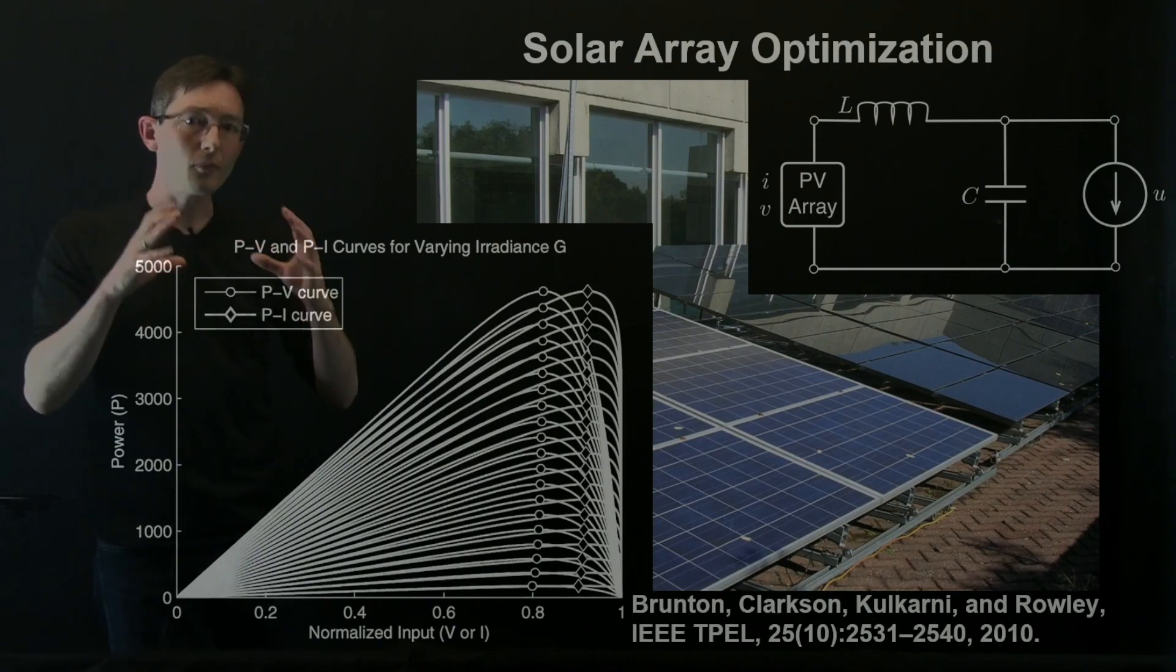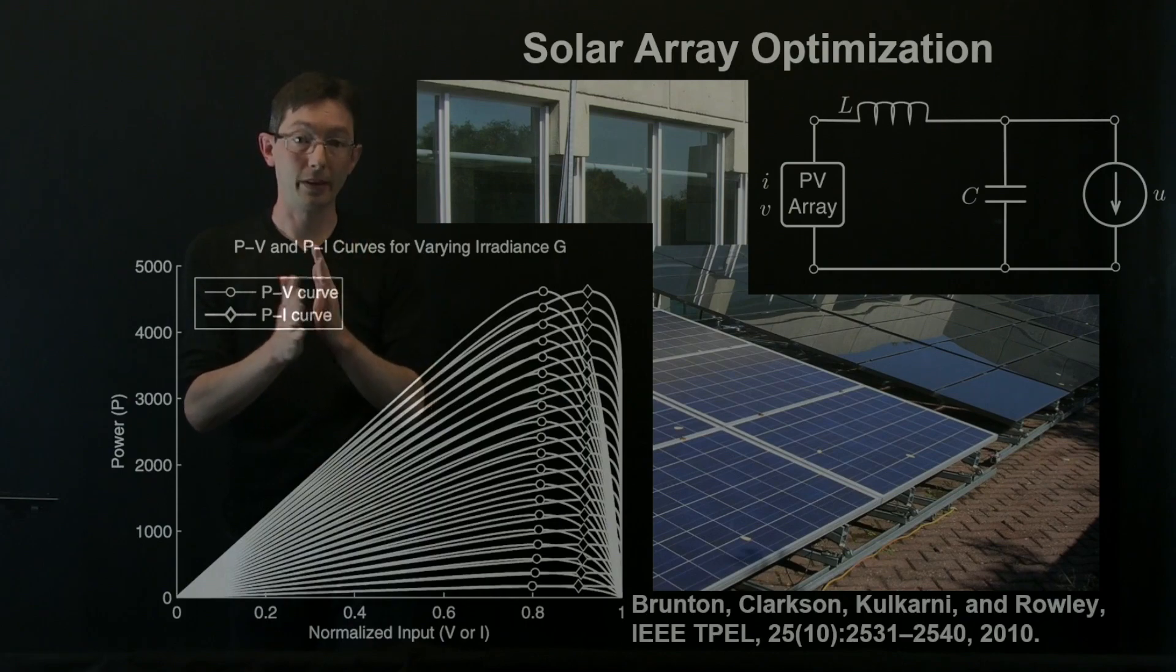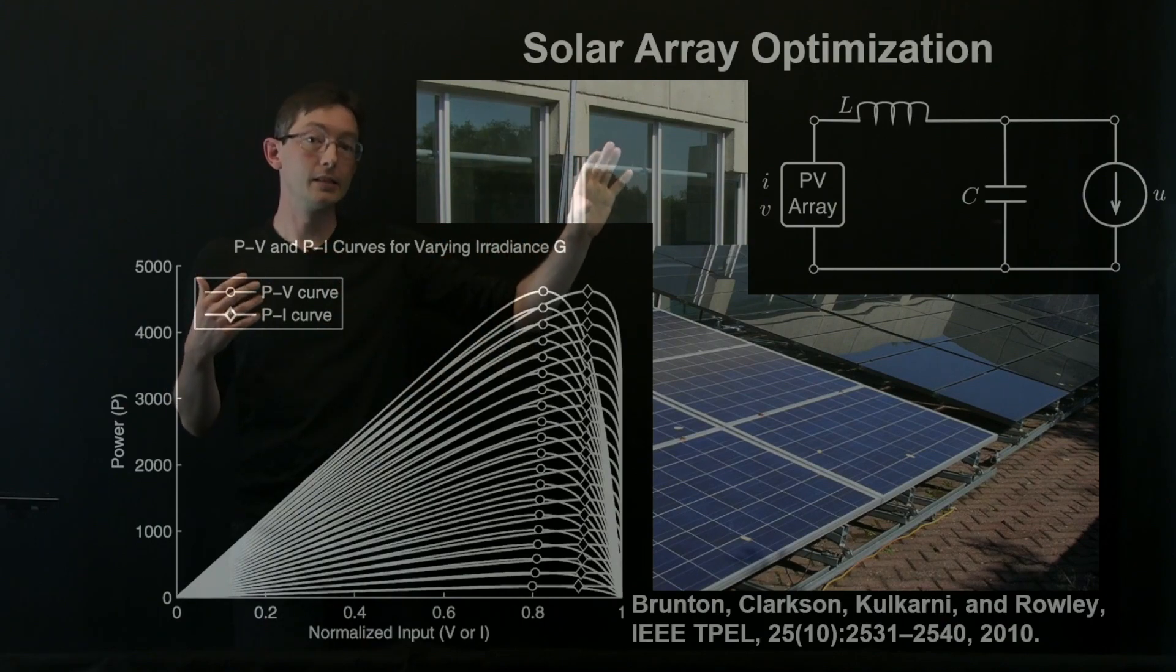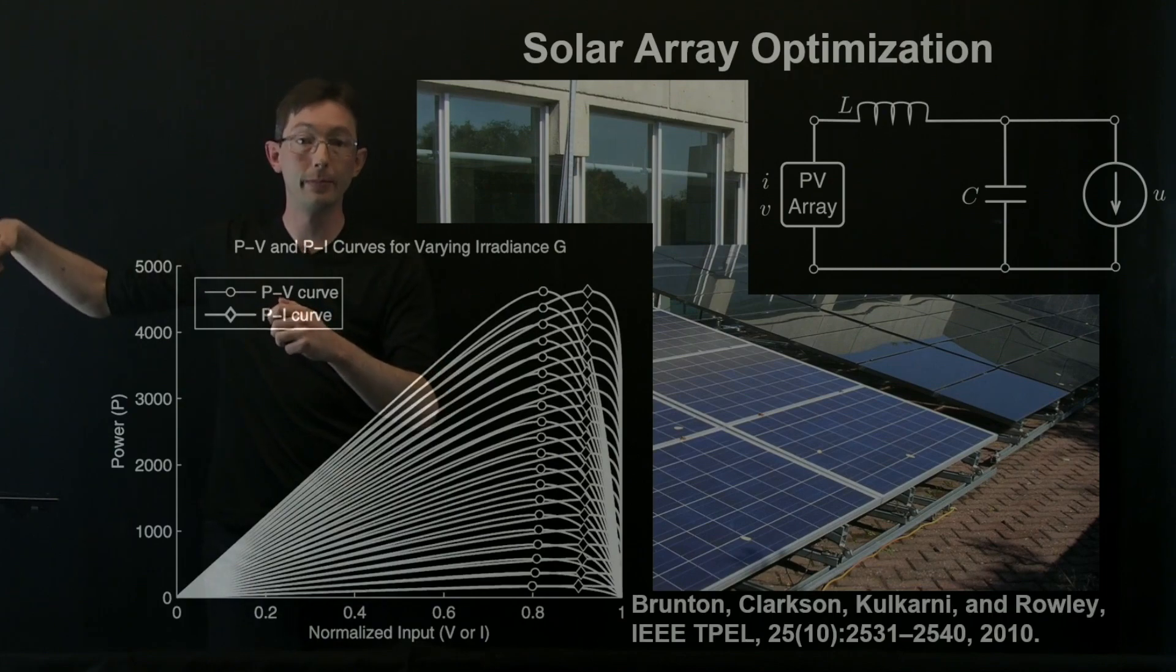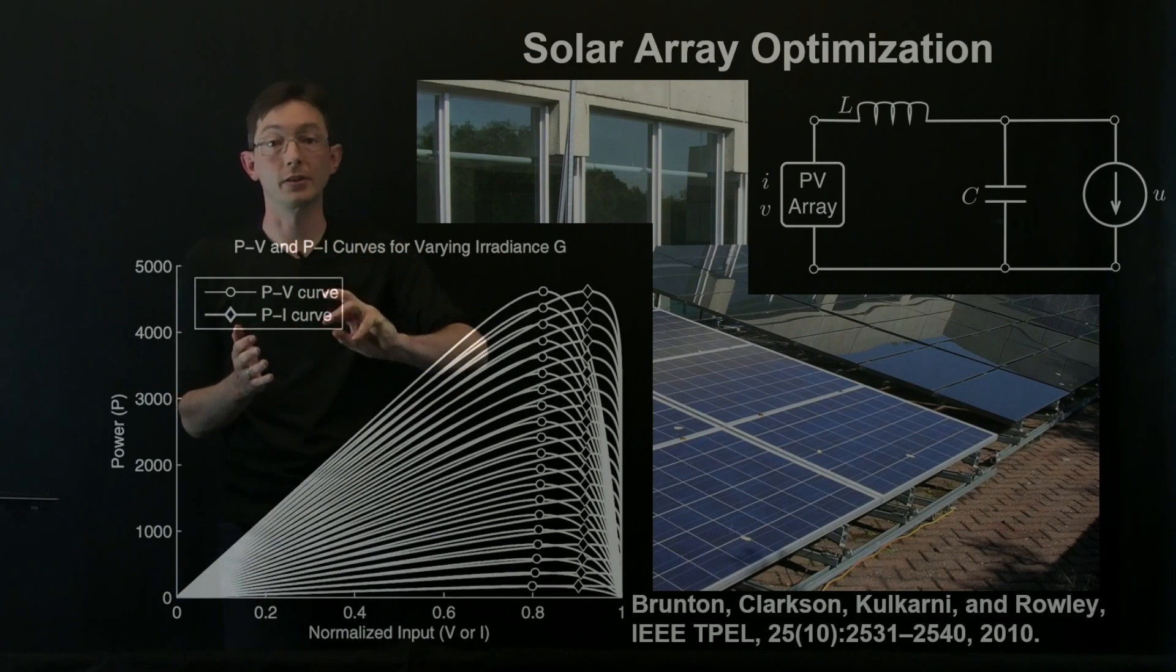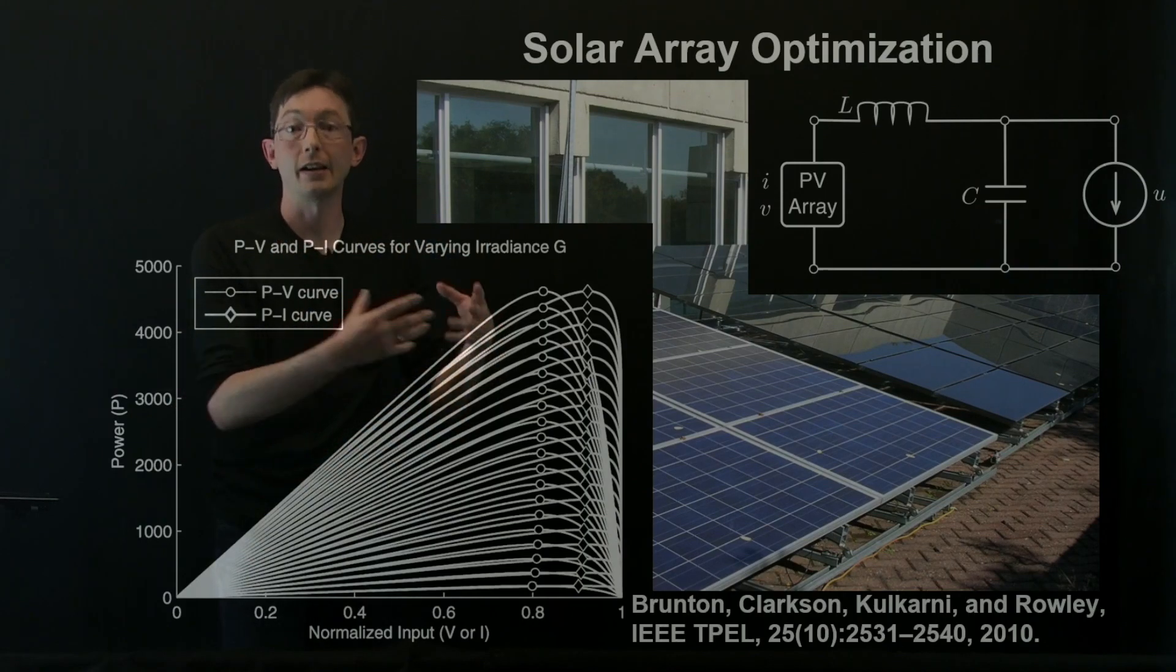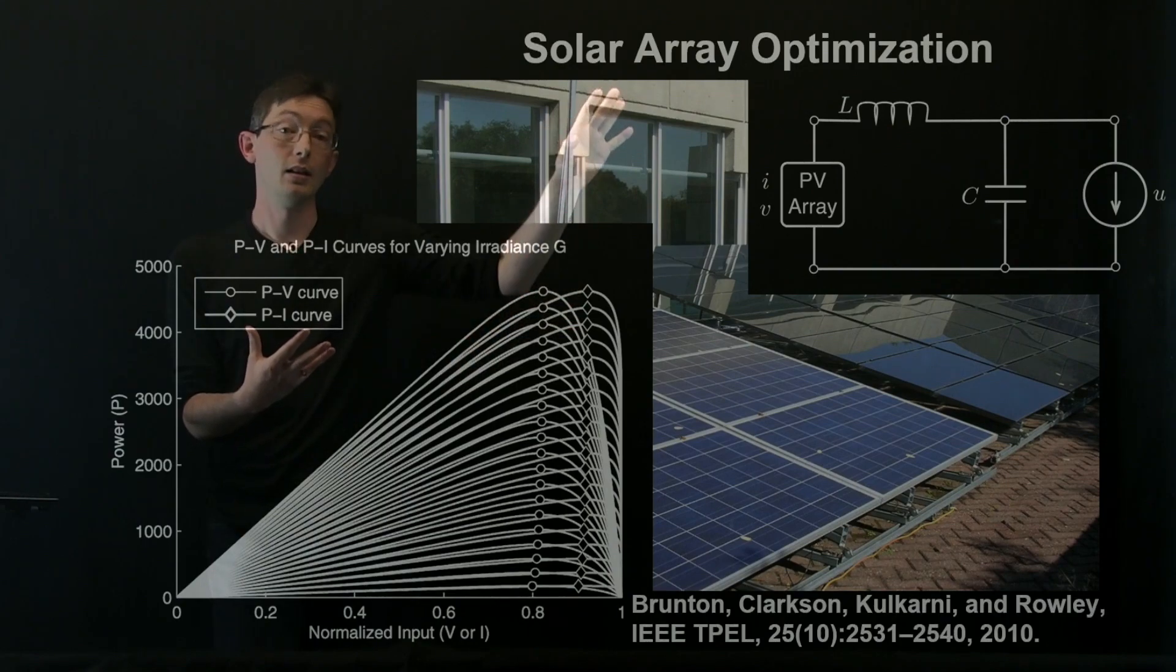Now again, this grid tie inverter that we were using at the time, by nature of the fact that it's chopping this up into a 60 hertz AC sine wave means that we get this natural sinusoidal ripple on top of our control signal and we can measure did our power go up or down based on those swings in the rippling input signal. And so we use that to design an extremum seeking controller to maintain peak performance in this array.